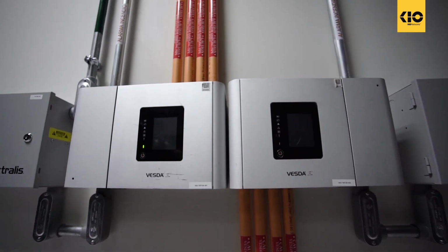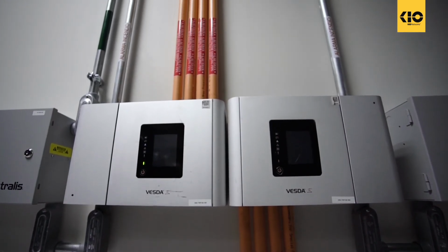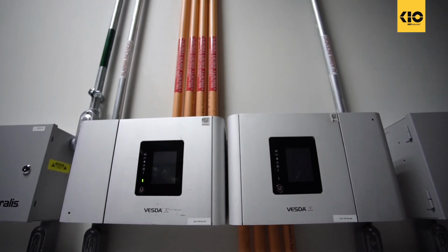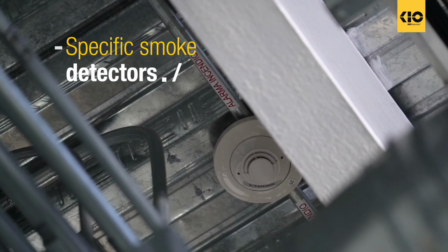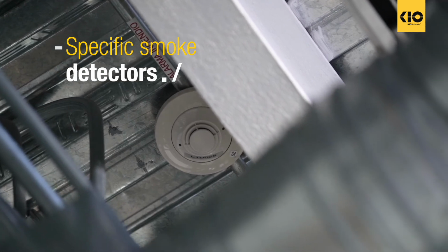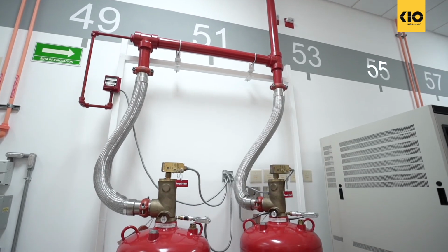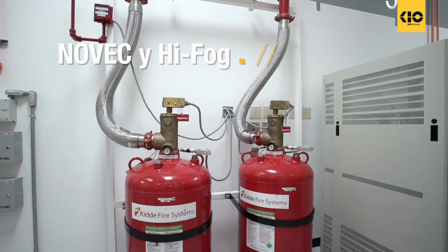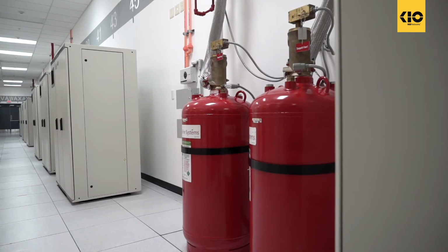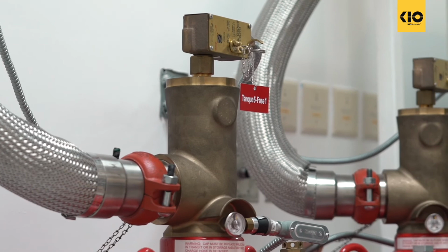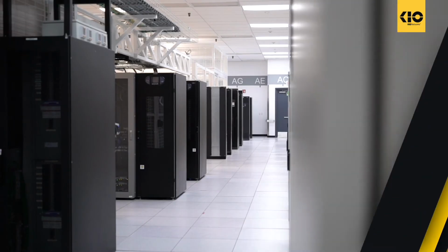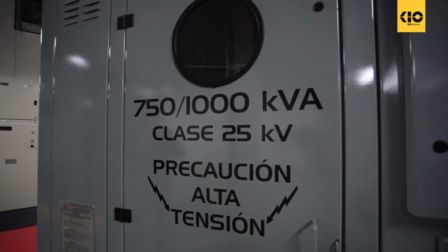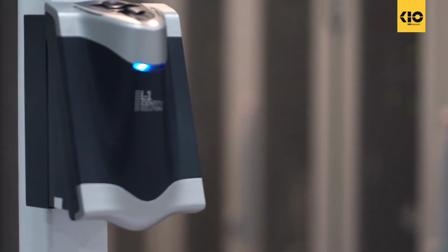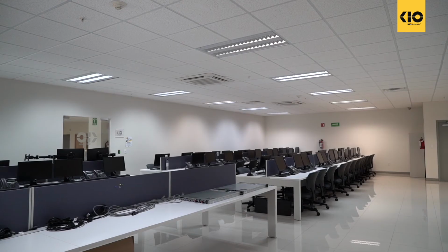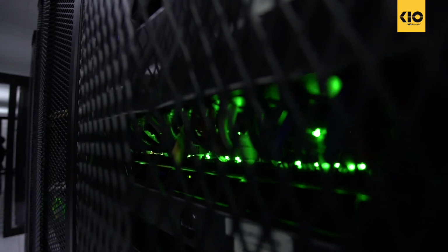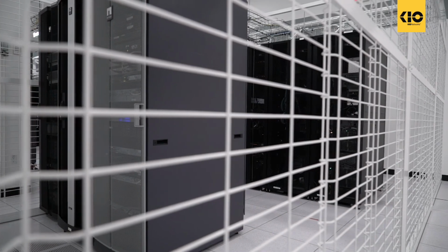It works through a suction system and an intelligent analysis console scanner which evaluates the air particles and quality. To complement the detection, we have specific smoke detectors throughout the building. Fire suppression is through clean agents Novec and Hi-Fog, as well as a pre-action dry pipe dual interlock sprinkler system in compliance with NFPA standards. The professional operation of the redundant electrical, cooling, communications, security, and safeguard systems previously seen allows us to provide the high availability required by technological solutions with different hosting options.